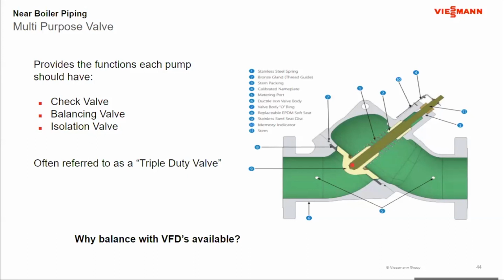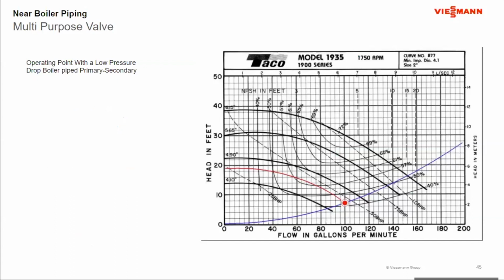Okay. Now, a lot of times we see the multifunction or the multi-purpose valve not being utilized, and part of the explanation is, well, we don't really need to balance it because there's going to be a VFD on the pump. Now, the recommendation is, regardless of whether we're doing a VFD or not, the balancing valve still should be utilized. And I'm going to give you an example of why with a pump curve.